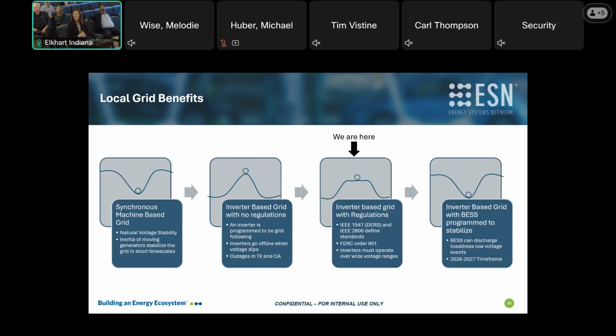There's also something called electrical stability, which is a lot of information, most of it not really relevant to Indiana. When PV was first put on the grid in California, Texas, and Spain, there weren't many rules about what voltage range inverters had to be set for to remain stable, so they tended to trip off whenever voltage dropped. That causes instability: a generator goes down, voltage drops slightly, and all the PV systems shut off in response. Spain had a big blackout this summer possibly linked to that, and California and Texas each had smaller versions that didn't get as bad. NERC has since addressed that.